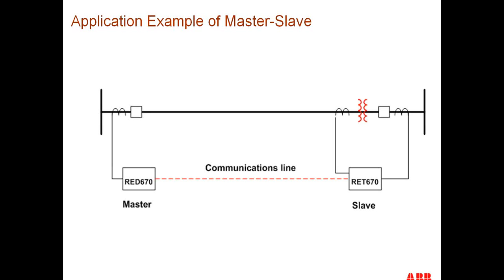A question came up again: in the future, which protection is going to be most used as the principal protection, differential or distance? I guess different people have different thoughts on this, but since communications are getting so easy to come by now, with one or more fibers available, and the number of settings you have to have on a line current differential relay versus a line distance relay is so much less, there's always going to be a place for line current differential relays in the future, and they may even surpass distance relays. And even NERC requirements may want you to have two different principles on line protection, where you can have a line current differential over one channel and a line distance over another channel. So there's definitely a place for that.